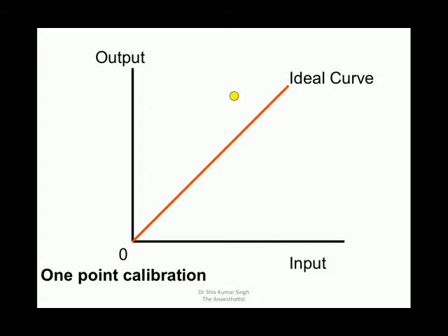So what can you infer from this? Is this machine accurate? Is it precise? No, we can't tell, can we? Now let's assume that the 0 is 0 and the line actually passes from 0 to the measured value. And if you look at the graph, there is a slope. This is called a slope drift. The machine has got a slope drift.